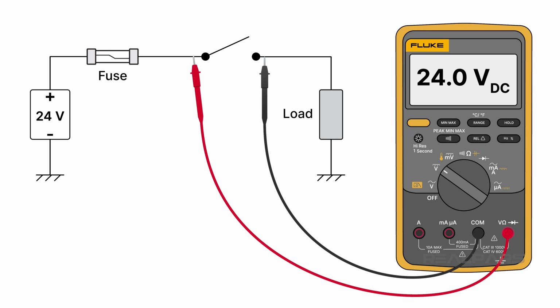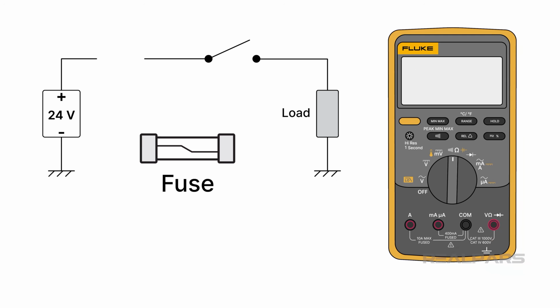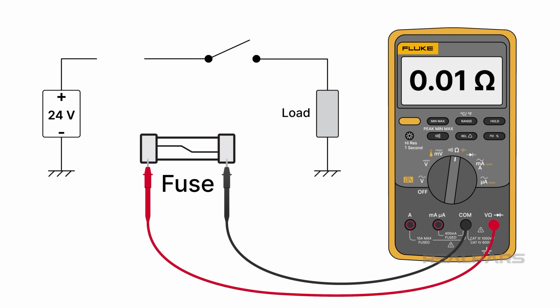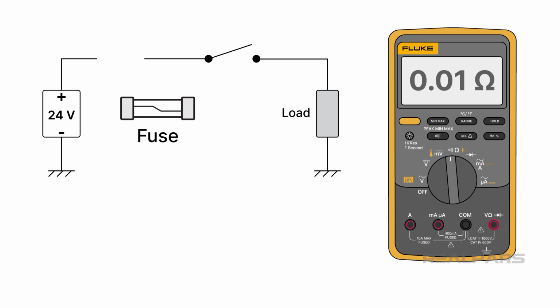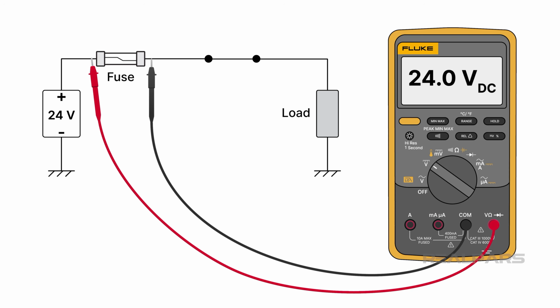Voltage measurements do not require disturbing the circuit under test. Components need not be removed, and wires need not be cut. For resistance measurements, the component must be completely isolated, providing the only current path between the two multimeter leads. Consider a voltmeter connected directly across a fuse that indicates 24 volts. The fuse is blown. Would you bother to remove the fuse and test it with an ohm meter?